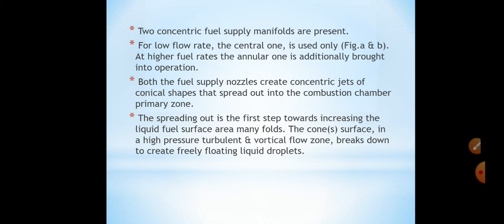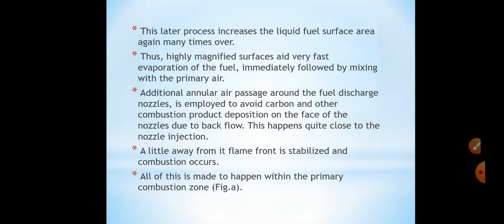The cone's surface, in a high pressure turbulent and vortical flow zone, breaks down to create freely floating liquid droplets. This latter process increases the liquid fuel surface area many times over again. Thus highly magnified surfaces aid very fast evaporation of the fuel, immediately followed by mixing with the primary air.